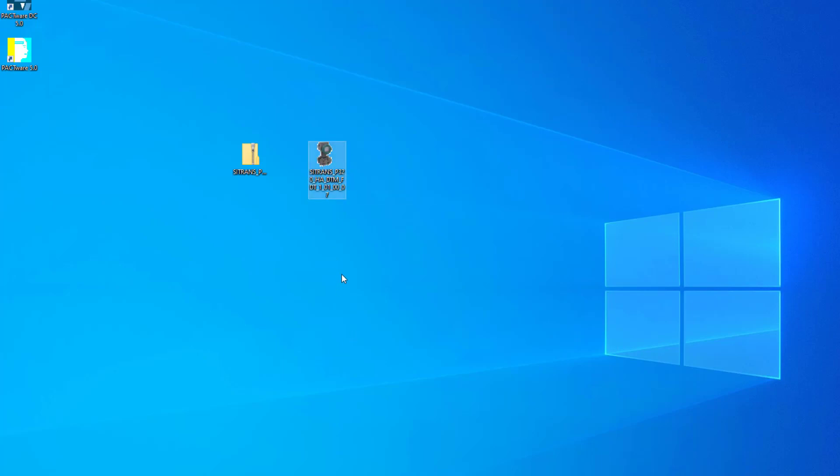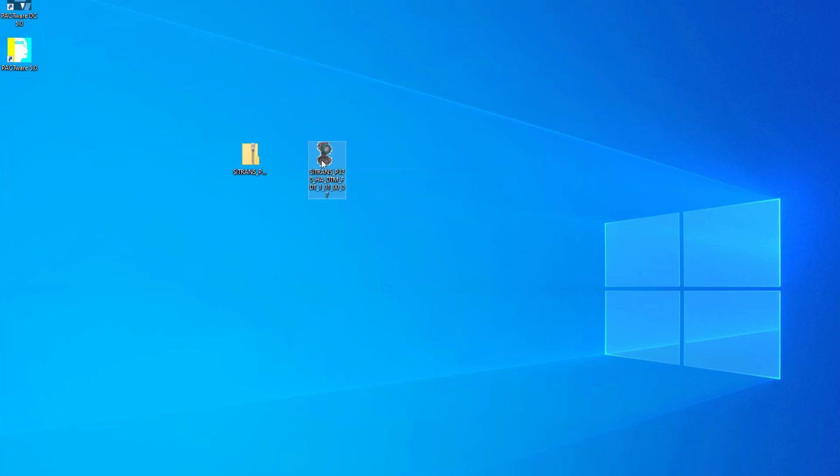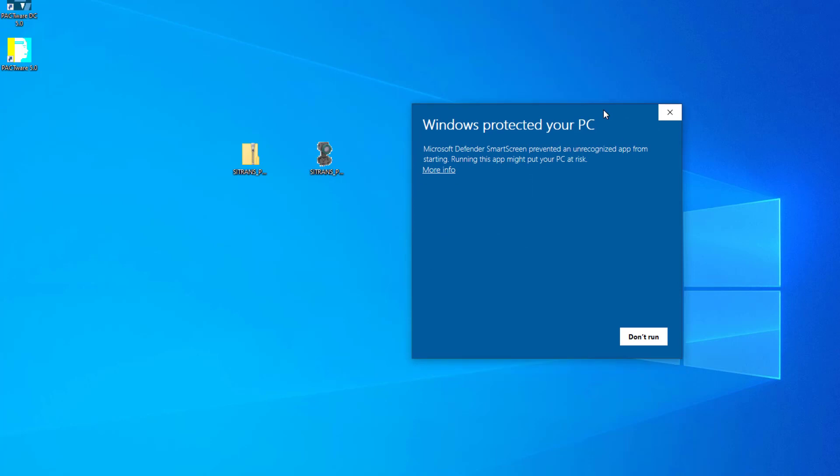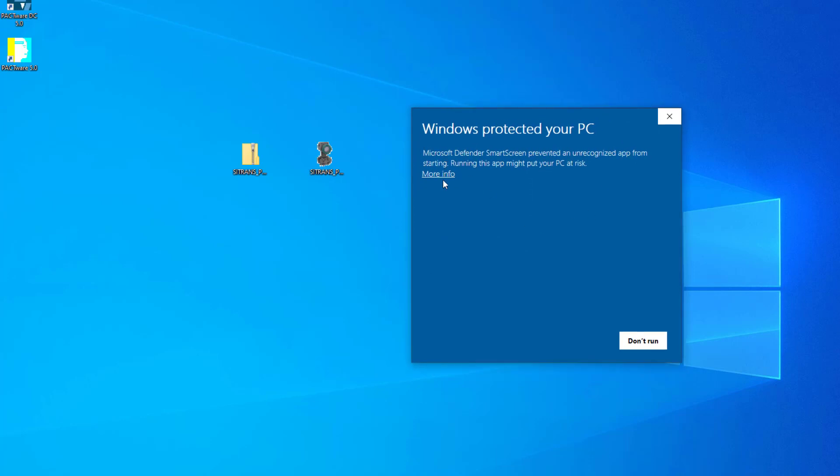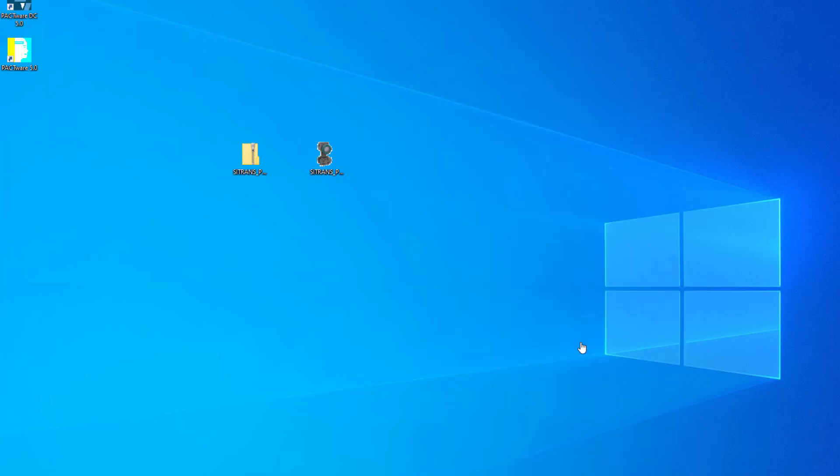Now this is where I think maybe PDM, Simatic PDM has the edge, because it uses a device catalog tool to import the EDDs and you don't need admin rights for that. What I've found with installing the DTMs, because they're a self-contained install file, you need admin privileges. And if I come over here, look, I'm getting this message again. I wouldn't have this with the PDM device library manager. But you do need to have admin privileges. That's really important.